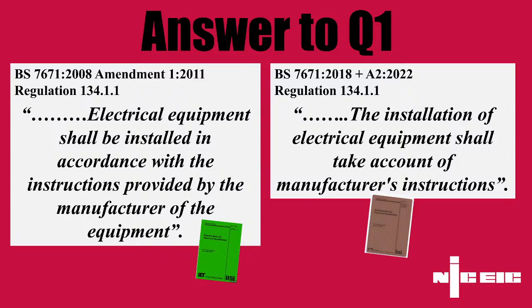I mean, in those situations we would always recommend you go back to the manufacturer for clarification, especially where you're considering that it would be better, i.e. compliant and safer, to not follow a particular point in the instructions. Always go back and seek clarification, but it has changed that regulation to confirm that you don't actually have to follow the manufacturer's instructions in order for your installation to be compliant with 7671.